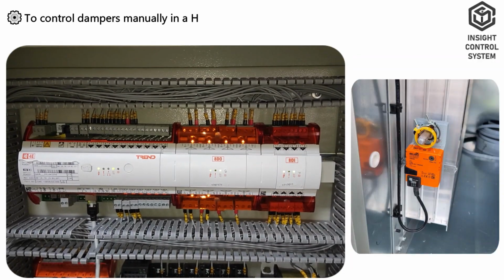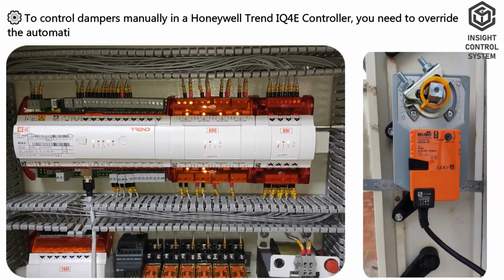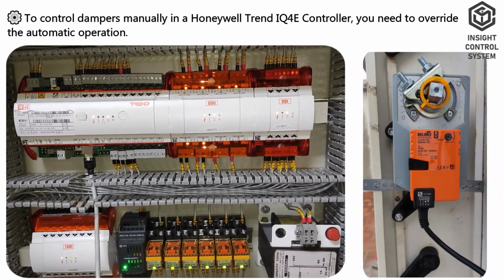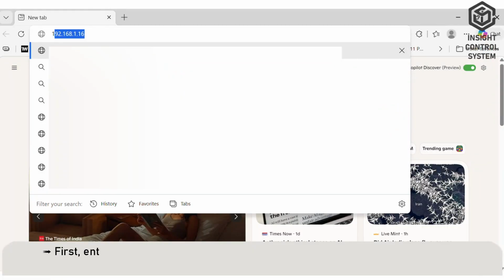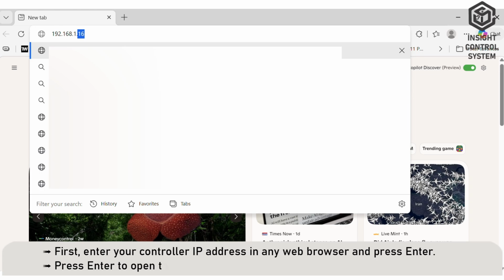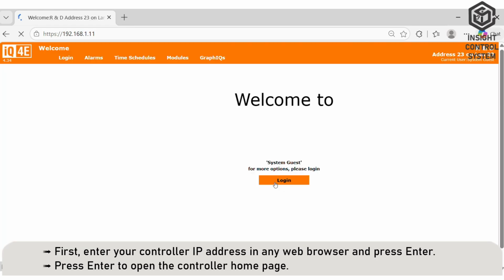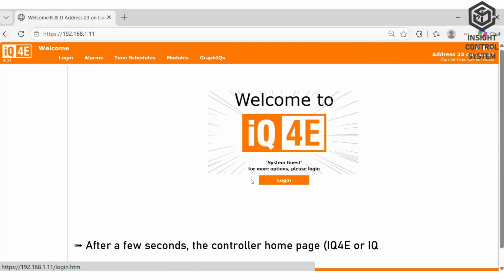To control dampers manually in a Honeywell Trend IQ4E controller, you need to override the automatic operation. First, find your controller's IP address and enter it into your web browser. Press Enter to open the controller homepage. After a few seconds, the controller homepage, IQ4E, will appear.